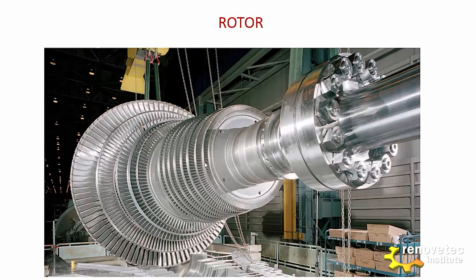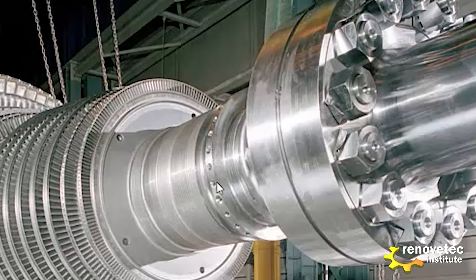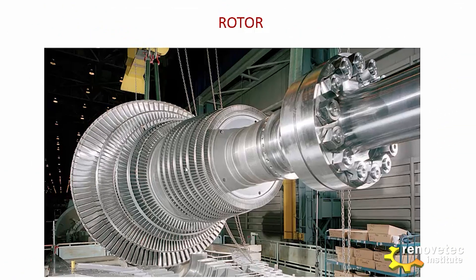And here, this is the low pressure turbine — two turbines connected: intermediate turbine and low pressure turbine. Here we can see another inlet; in this space we receive another inlet of steam. See this orifice — this orifice is used to install a special weight to balance the rotor. At the outlet there is another similar orifice also used to balance the turbine.